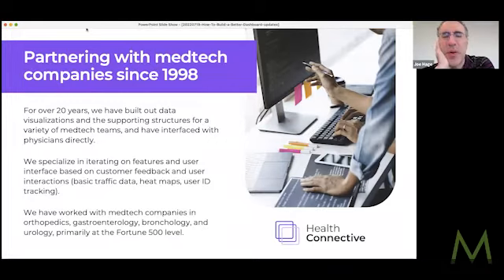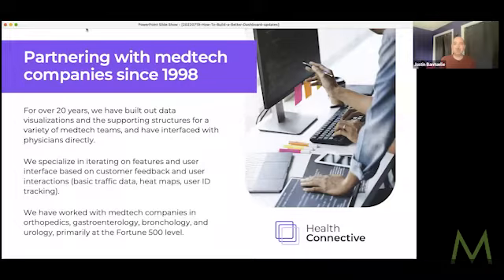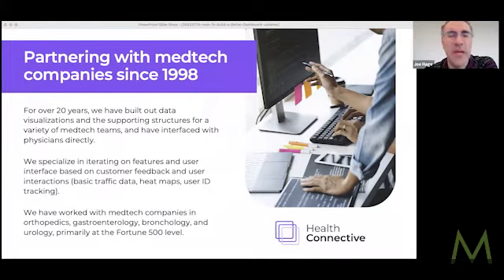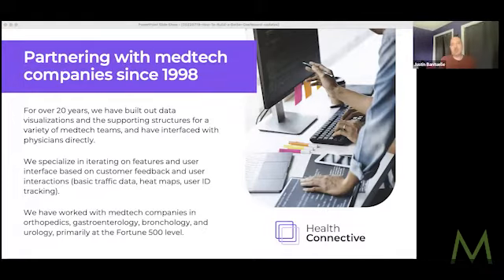That's interesting to me. Why wouldn't you be SaMD? So software as a medical device is a very specific designation that requires a tremendous amount of overhead and administrative burden to prove. When your software is a medical device, that means your software is critical to the operation of the medical device itself, like in the OR. Our software typically can't affect the procedure itself, so we try to dodge that designation and make life easier for everyone.